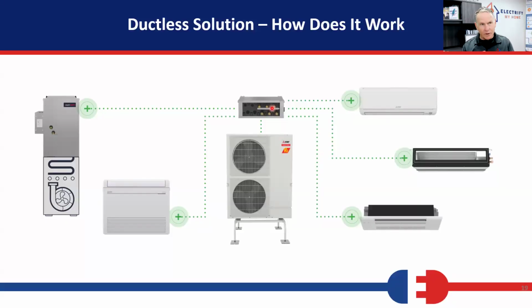And now with copper at an all-time high price and vinyl line set at an all-time high price, this can get very expensive to install very quickly. There's a lot of pieces of equipment. Multi-zone outdoor units are considerably more expensive than single-zone outdoor units. And then we have the BTU sharing issue. So let's just say we're going to put 5 wall mounts in a 3 bedroom house. We're going to put one in each bedroom, and two in the living spaces.